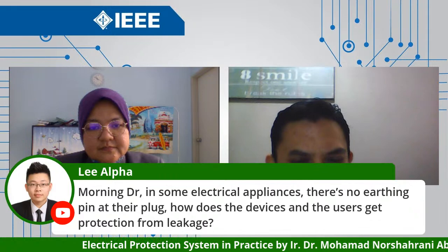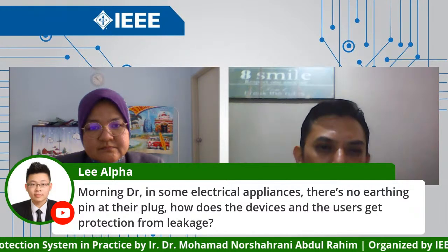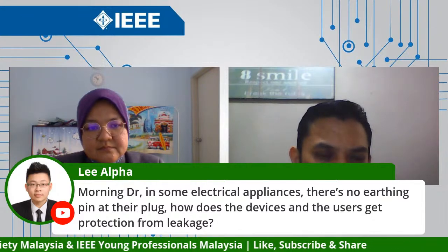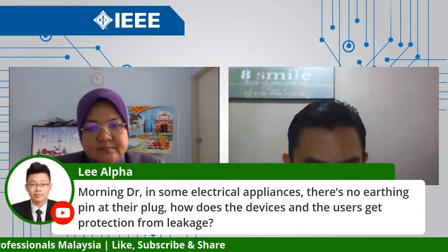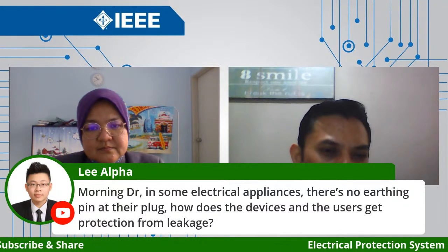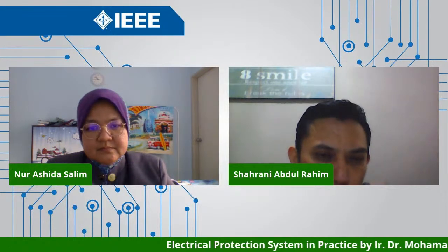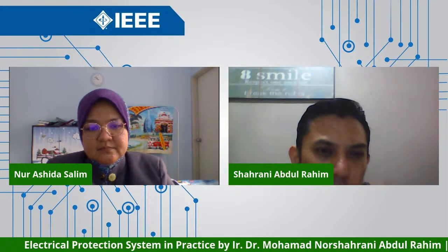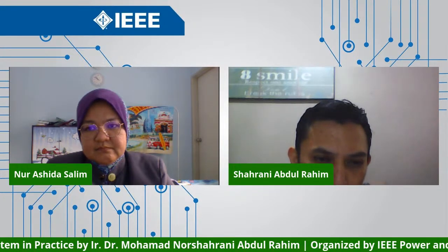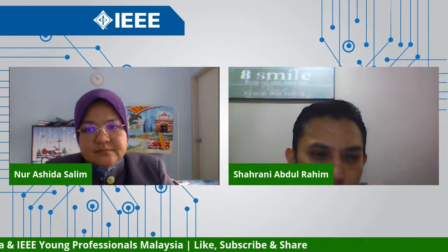Okay. So we just simulate, once there is a leakage current in the system, it will leak to the body. We have a phase and neutral line, so the leakage current will find the way to the source, as I showed in the previous slides. So even the neutral line finds the imbalance in the return current, and the RCD will cut it as a residual. The concept is still on the RCD, which is residual current.